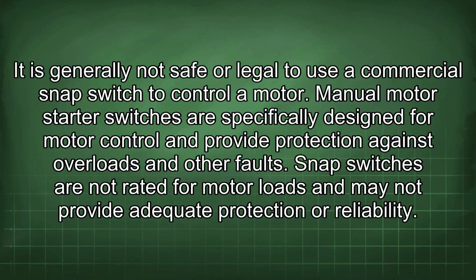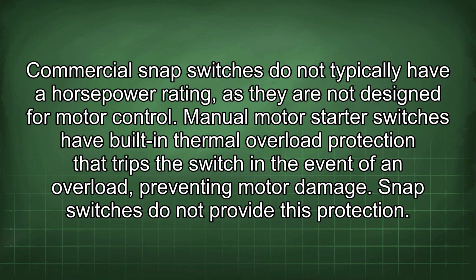It is generally not safe or legal to use a commercial snap switch to control a motor. Manual motor starter switches are specifically designed for motor control and provide protection against overloads and other faults. Snap switches are not rated for motor loads and may not provide adequate protection or reliability. Commercial snap switches do not typically have a horsepower rating, as they are not designed for motor control.